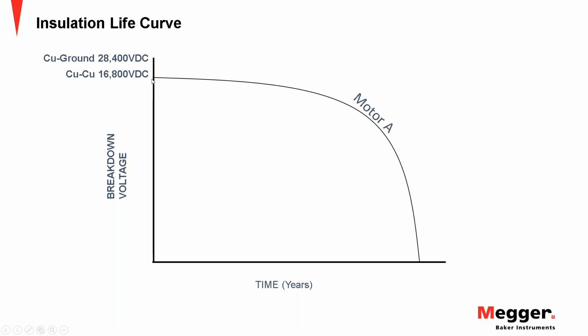We've mentioned that several times. I'll go into why that value is so high now. But then over time, as we put the motor into service, that breakdown voltage is going to degrade as the heat affects the insulation. Eventually, it's going to lead to motor failure once the insulation can no longer withstand the switching surges that I discussed earlier, or of course, once it drops below the bus voltage, then it's just going to fail either to ground or phase to phase or wherever that insulation is weakest.